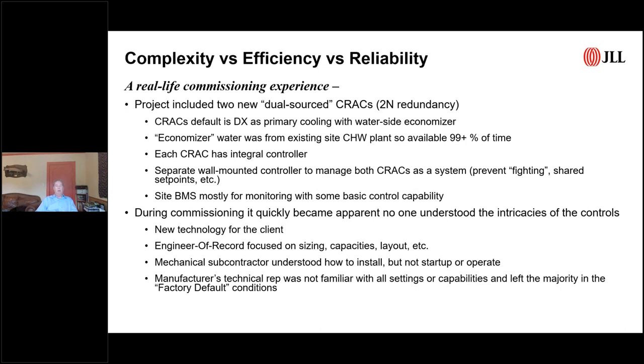In our case, we plugged the economizer into a chill water plant, so it was actually available 99.9% of the time. Each CRAC unit had an integral controller. There was a separate controller on the wall that managed the two units together as a team, so they could share set points and wouldn't fight with one in heating and one in cooling, etc.